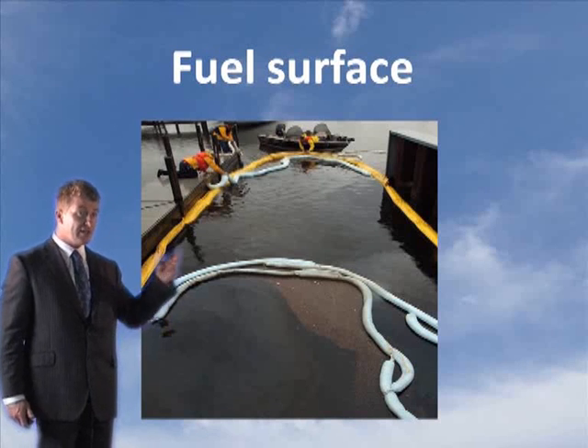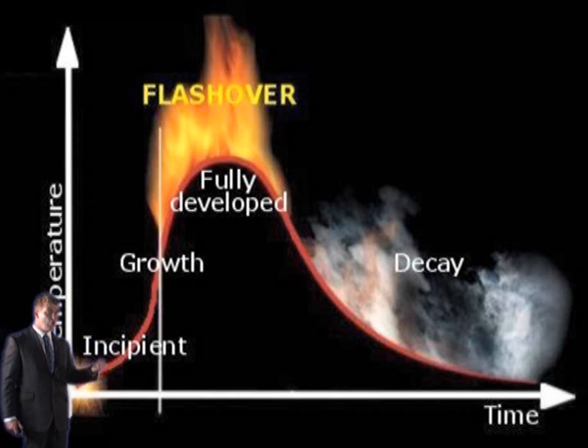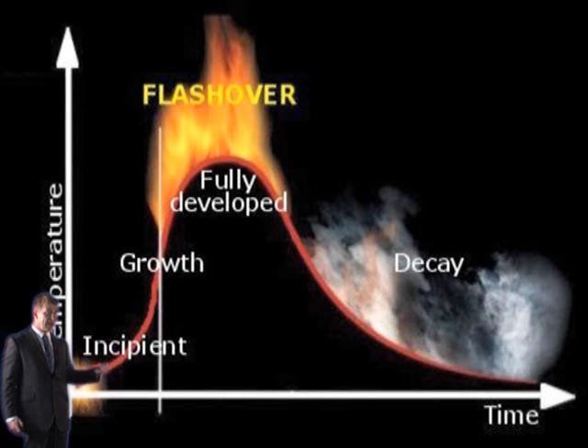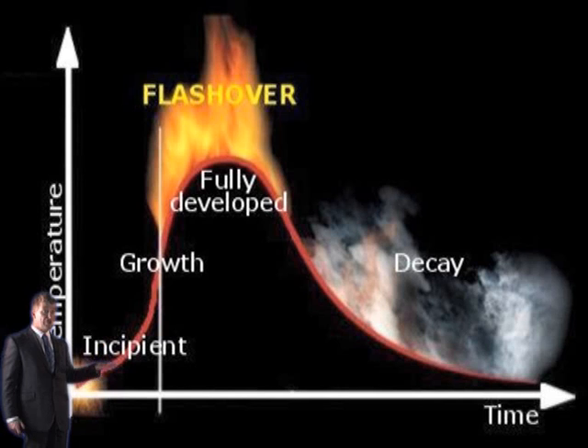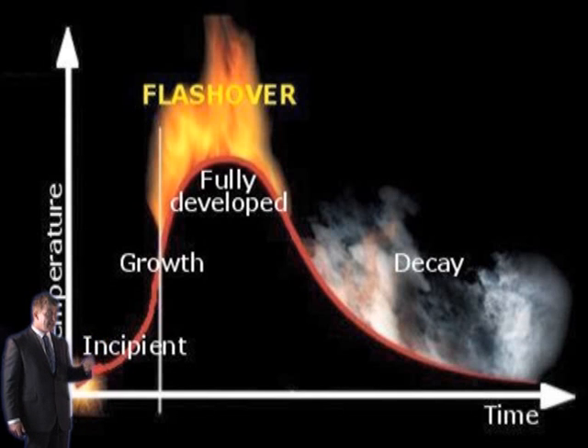As you can see on this chart, firstly you get induction and followed quickly by ignition. Then you've got your growth phase depending on the type of fuel and the ventilation conditions. Next you're going to get is a flashover. That is followed by a fully developed fire with maximum heat release, maximum temperature, and then you get your decay phase.